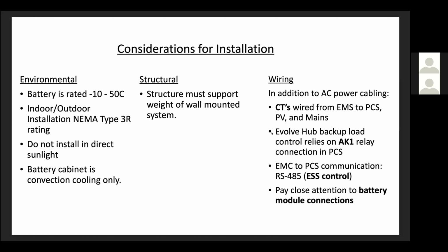Keep in mind that the Evolve Hub backup load control relies on AK1 relay connection inside the PCS. That relay wiring is a simple plug and play two wire run, but it is provided with each system and is at a fixed length. And unless you want to end up doing extra wiring, locating the Evolve Hub itself within no more than about 2 feet to the left of the PCS, as shown in the installation guideline, is your best bet. It will save you on installation time. Again, please read the manual.